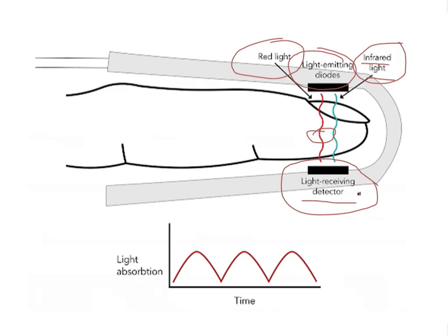For example, at certain ratios, they found that the oxygen saturation will be 97%, at another ratio 90%, 80%, and so on. We have to pay attention that any concentration of hemoglobin with oxygen less than 70% will not be accurate, because it's unethical to decrease the oxygen saturation in volunteers below 70%.